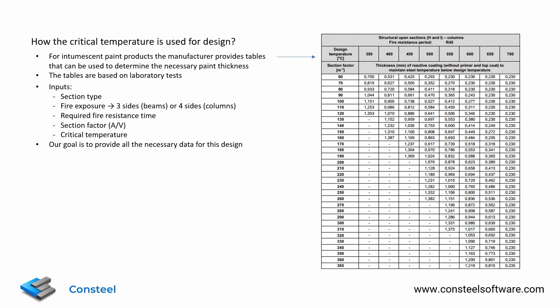To use one of these tables, we need to know the section type, the fire exposure, the fire resistance time, the section factor and the critical temperature. With these inputs, we can finally determine the required paint thickness and ensure that our structure is able to carry its loads until the required fire resistance time.